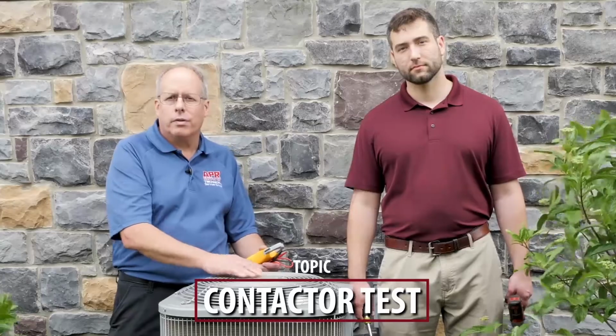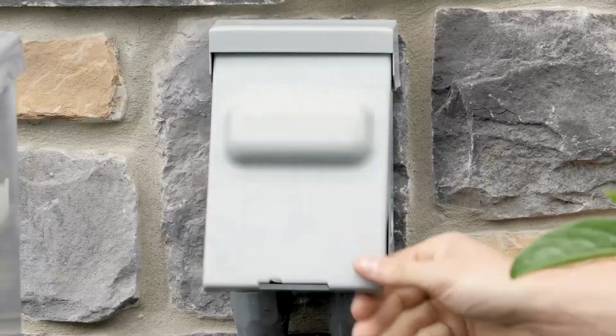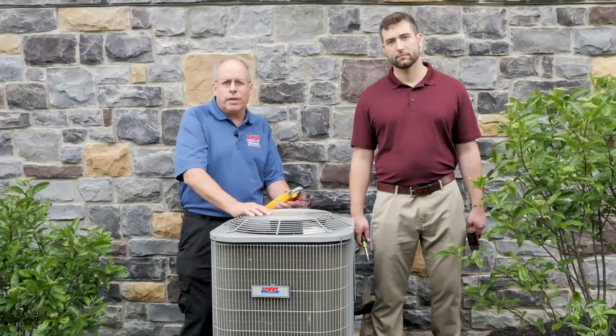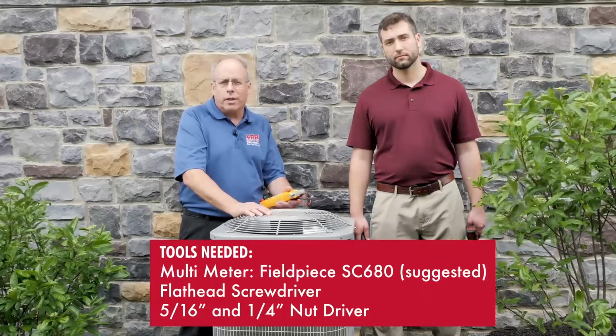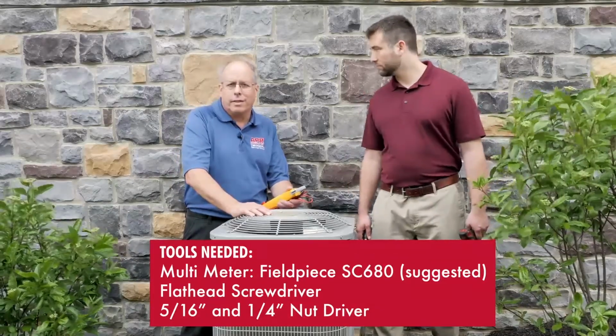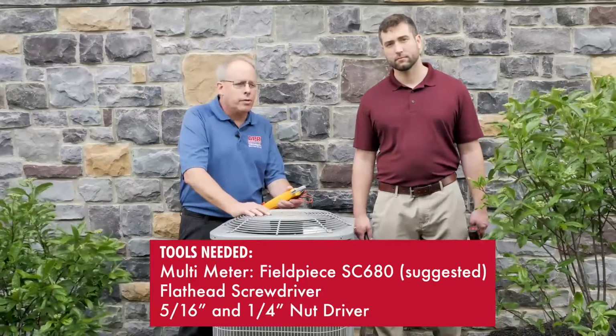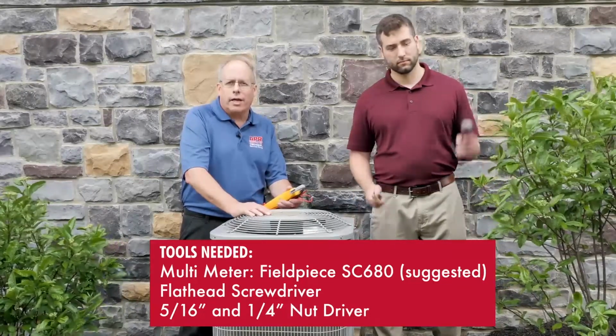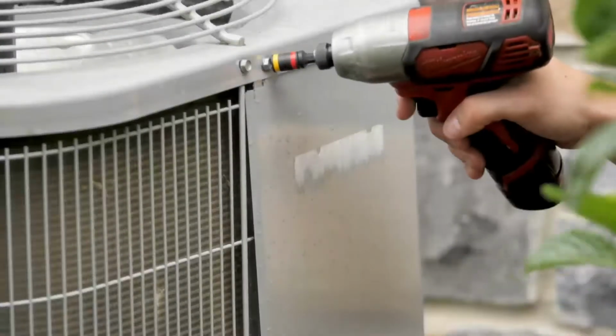Today we're going to be testing the contactor of the condensing unit. This will be both high and low voltage, so we will be disconnecting the high voltage power for safety. The tools you need for this will be a good quality multimeter. We're using the Fieldpiece SC680. You'll need a flathead screwdriver and a nut driver to gain access. Open the access door on the side of the condensing unit.